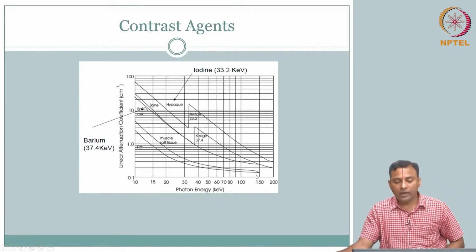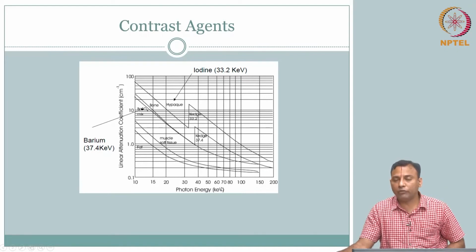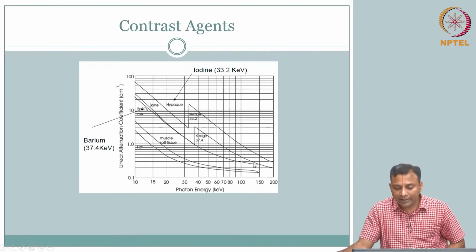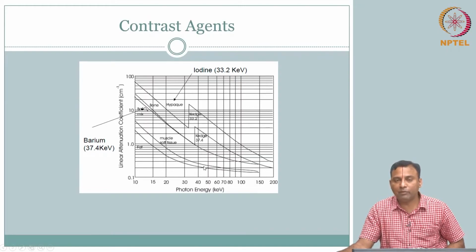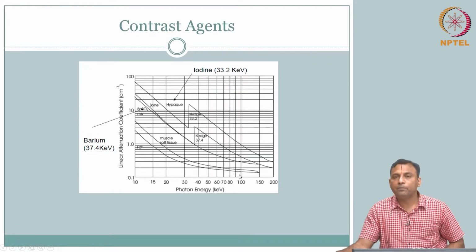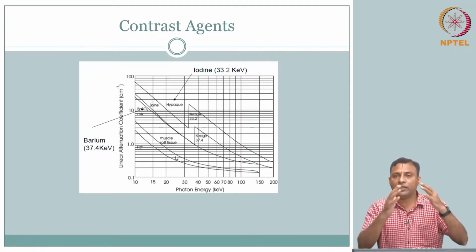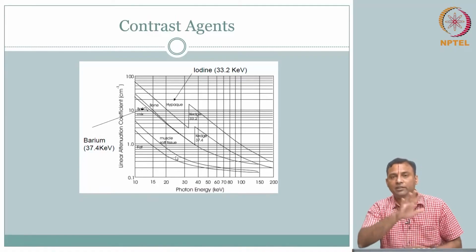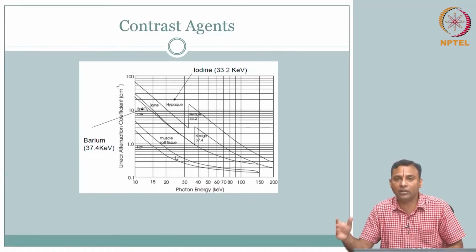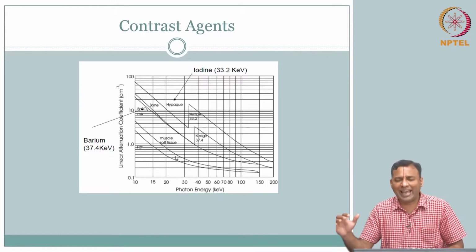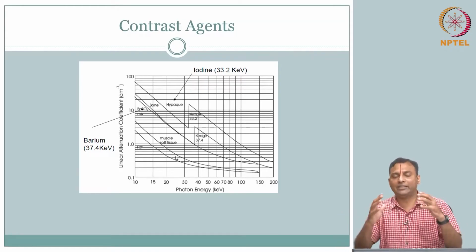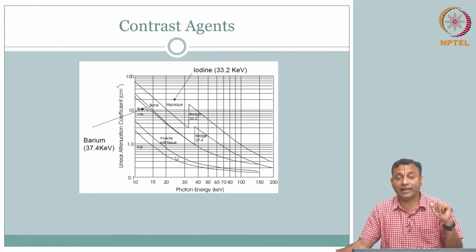And if the photon energy is too large, then the inherent contrast between the various materials, here for example bone, muscle and fat, is reduced. So there is a sweet spot in between. That's why our X-ray energy, remember the spectrum that we plotted outside the X-ray, all the filtering that we have done. So we have carefully come up with the X-ray energy that can maximize your interaction.